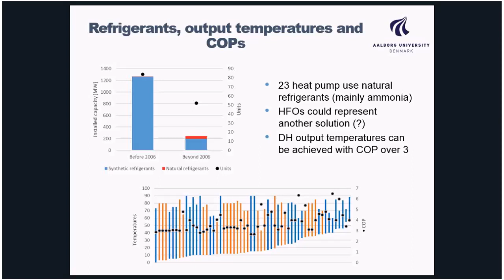The heat pump operation is also a very critical part of the future operation of heat pumps. That is because there are differences in how the heat pumps are operated. In Sweden, all heat pumps have been operated approximately 4,000 hours per year, while the newest heat pumps are currently operated 7,000 to 8,000 hours a year. This is important because it is closely connected to the component wear, the mechanical wear of the heat pumps.